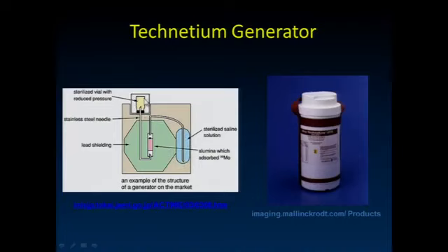And if you popped an evacuated vial onto the little needle, if you will, on the top of this, it would suck that fluid past that column, taking off the soluble technetium, and you'd end up with technetium in your vial, and hopefully it was working well, and you ended up with very minimal amount of breakthrough of molybdenum in your vial there.